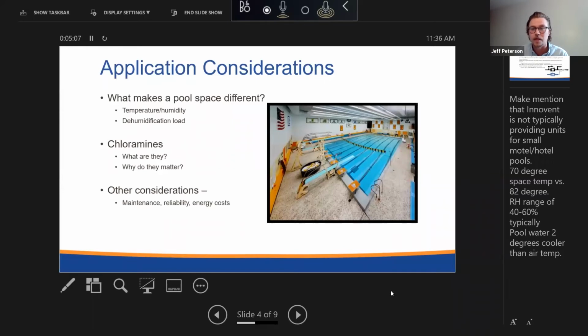I mentioned the relative humidity in the space, 40 to 60%. The water temperature is usually around 2 degrees cooler than the air temperature. We control to the air temperature because you want to make sure that swimmers who get out of a pool don't get super cold when they're walking around wet, right? You're most concerned about the comfort of the swimmers who are walking around rather than the spectators or the people who are coaching or something like that. But also, you want to make sure that the water temperature is 2 degrees cooler and that you don't have really cold air in the space.